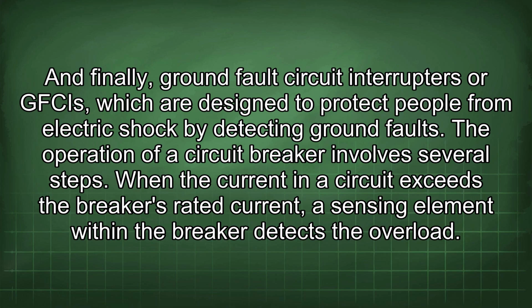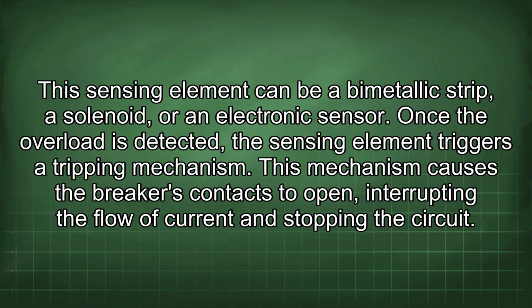When the current in a circuit exceeds the breaker's rated current, a sensing element within the breaker detects the overload. This sensing element can be a bimetallic strip, a solenoid, or an electronic sensor. Once the overload is detected, the sensing element triggers a tripping mechanism. This mechanism causes the breaker's contacts to open, interrupting the flow of current and stopping the circuit.